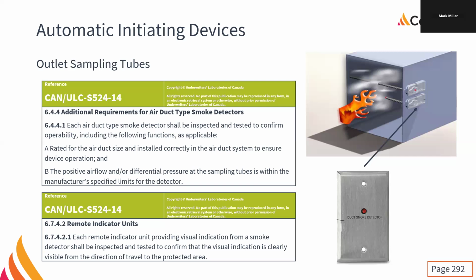LEDs. And it has to be installed so that the visual indicator, right, the remote LED, is clearly visible from the direction of travel to the protected area. Right, so we can't tuck this remote LED in a closet in the very back of the area. It has to be in the direction of travel. Right, so we have to be able to find it easily, because this is going to tell us which device has gone into alarm.